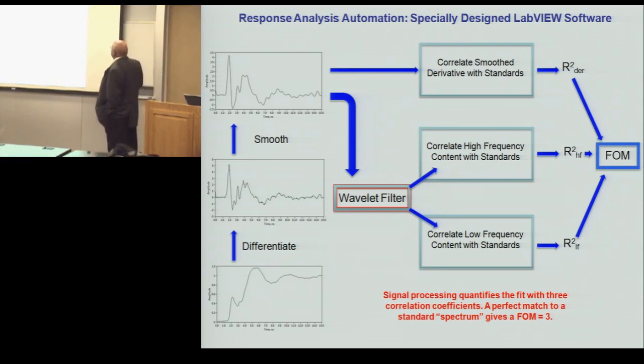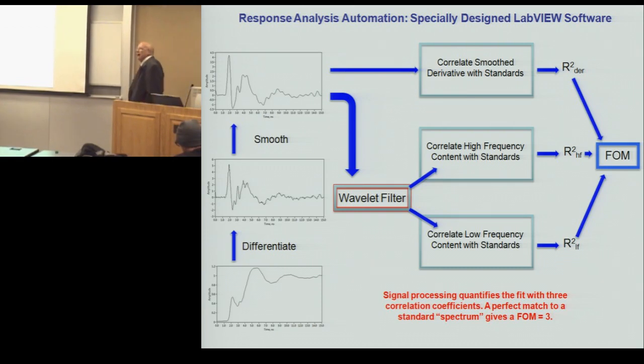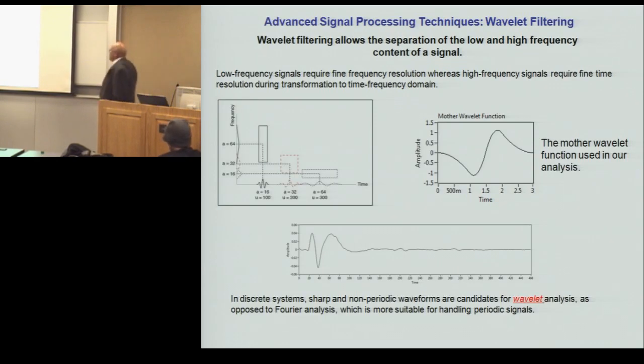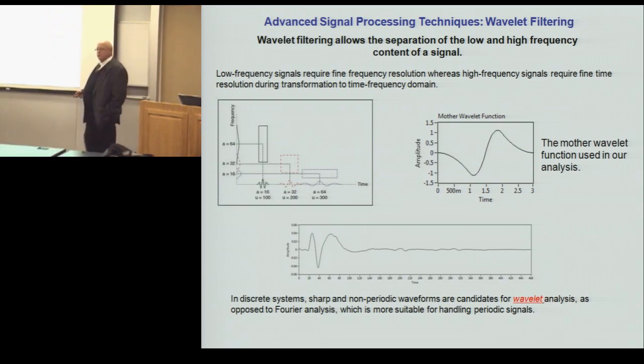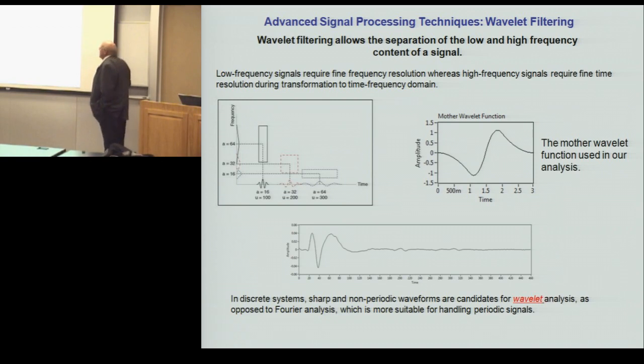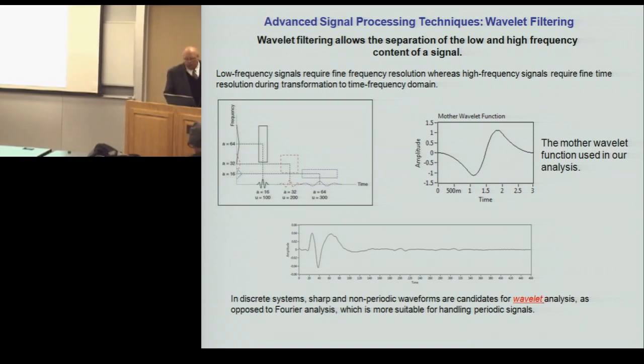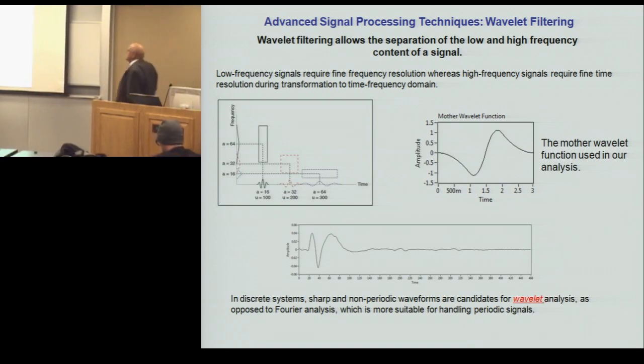The wavelet filter essentially allows us to differentiate high-frequency and low-frequency content in those waveforms, and then compare the wavelet-filtered standards to what we're getting under test conditions. From each of these we get a correlation coefficient. We sum those up to get what we call a figure of merit, which at maximum under perfect match conditions would give us three — one from each of these correlations. A comment about wavelet filtering: you might say, why not use Fourier transforms? Wavelet filtering tends to be more applicable for these kinds of signals and retains better resolution across the frequency spectrum.